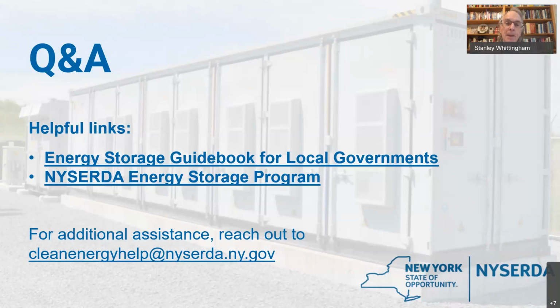The one thing I'll add, and we'll touch more on this in the fire safety webinar, is that with a large containerized system, you don't want poor management and gas detection that keeps the system essentially sealed, because that's when you get explosion risk. That's what happened in Arizona. Requirements around managing thermal propagation and explosion risk include sensing for released gases, ventilating, and making sure you don't build up an environment that could explode.